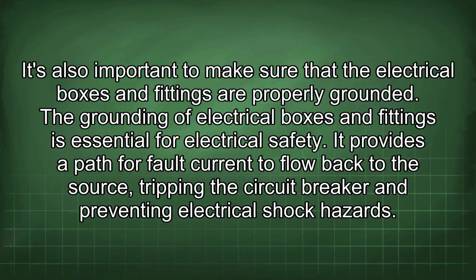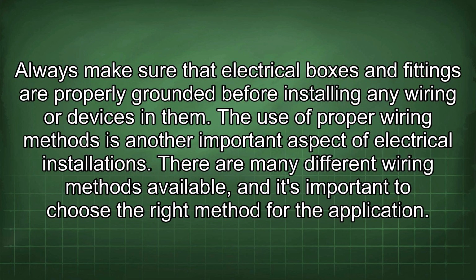The grounding of electrical boxes and fittings is essential for electrical safety. It provides a path for fault currents to flow back to the source, tripping the circuit breaker and preventing electrical shock hazards. Always make sure that electrical boxes and fittings are properly grounded before installing any wiring or devices in them. The use of proper wiring methods is another important aspect of electrical installations.